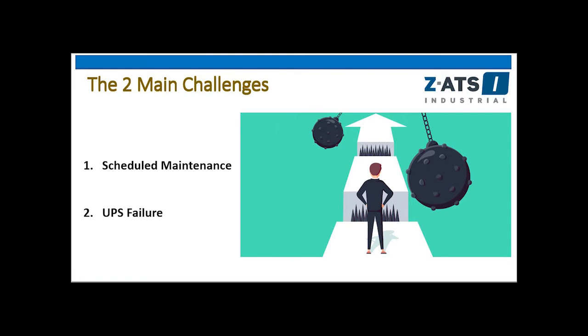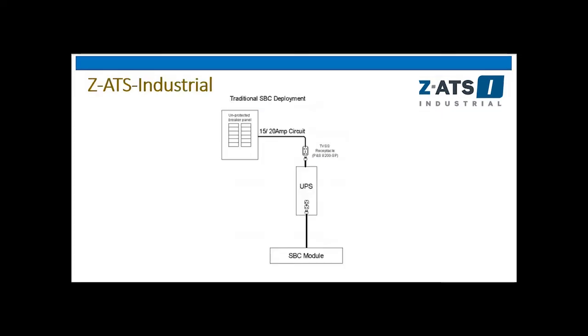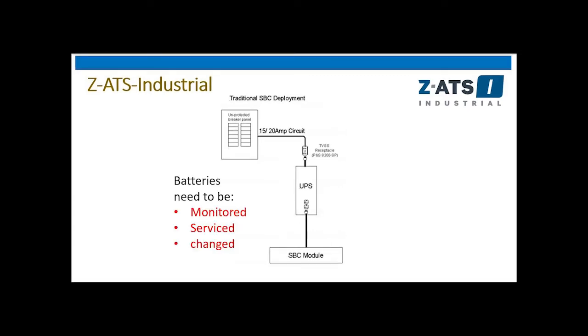Why is that? The reason is the way things are often laid out: you've got your UPS, you're feeding the panel with it, and attaching systems on the other side. Ultimately a UPS is just batteries with some logic, and batteries with intelligence still need to be monitored, serviced, and changed. If that's not done regularly, UPSs die, and whatever is on the other side often goes the way of the dinosaur along with that UPS.